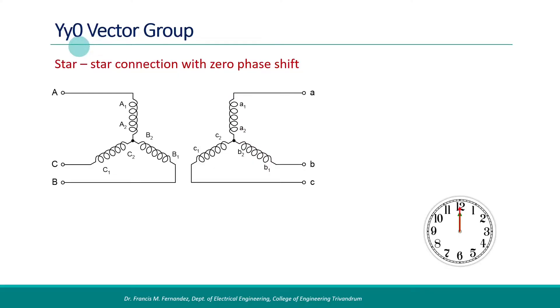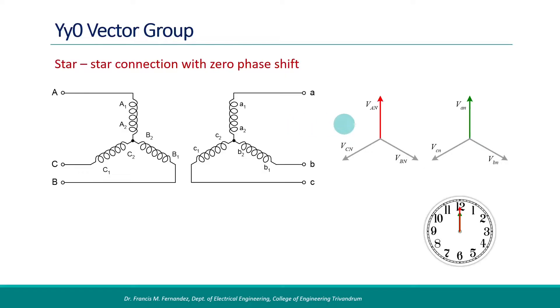The first type we are going to discuss is the YY0 vector group. It has a star-star connection — both primary and secondary windings are star connected. In the phasor diagram, the three voltage phasors are 120 degrees apart. The secondary winding voltages in all three phases are in phase with the corresponding primary voltages. The phase difference is zero and the clock position corresponding to that is zero hours — that is how we name this vector group as YY0.